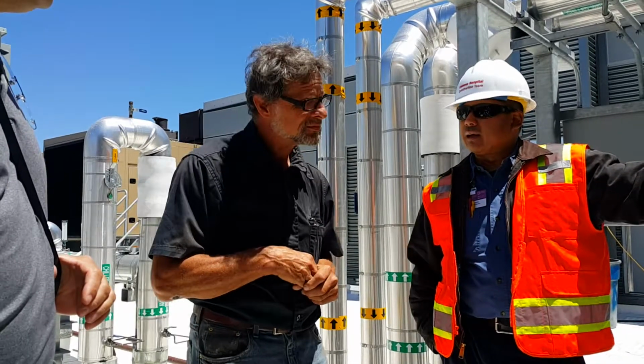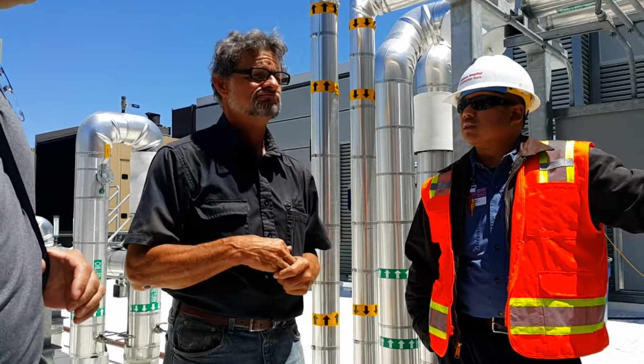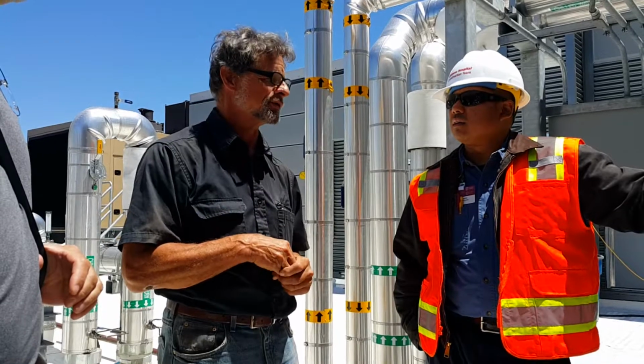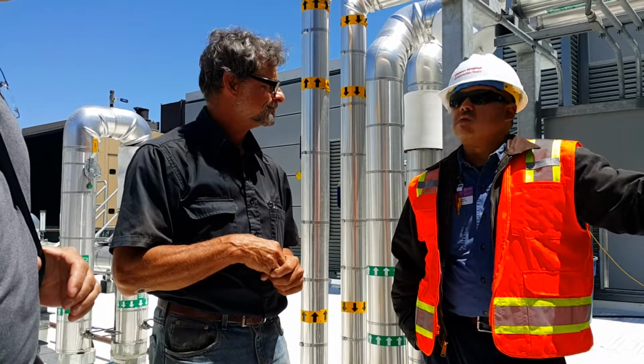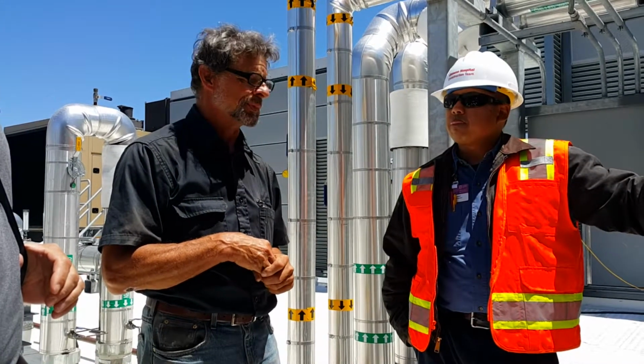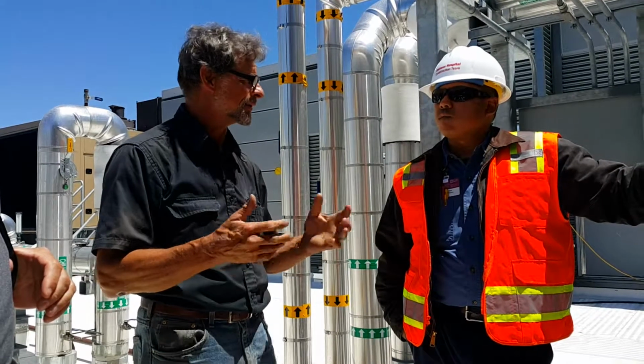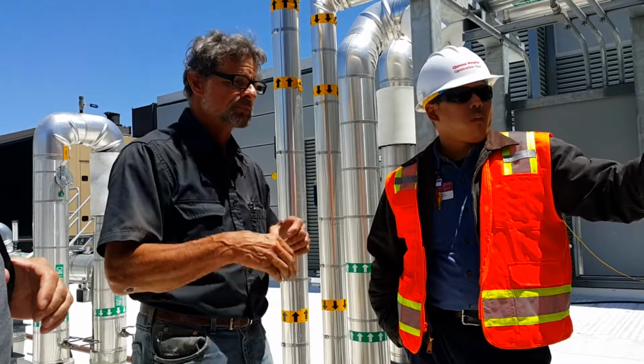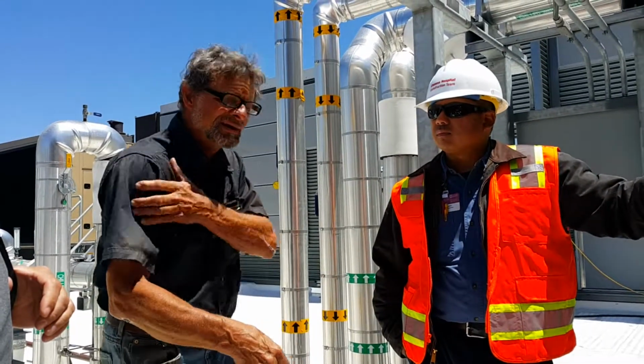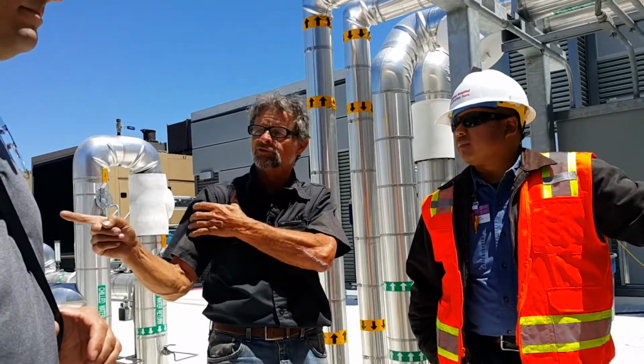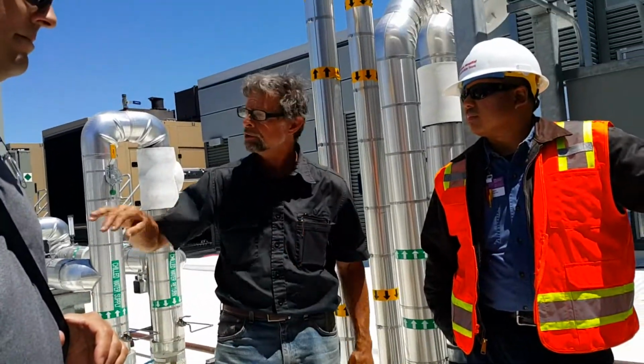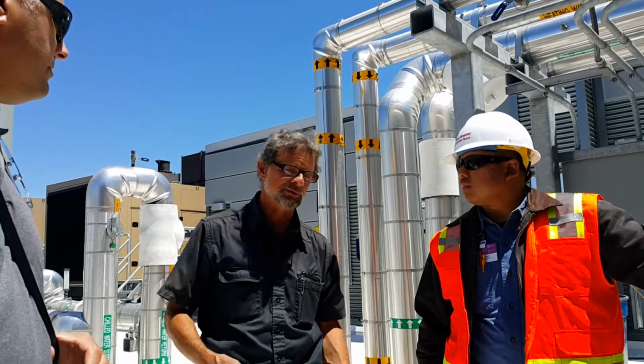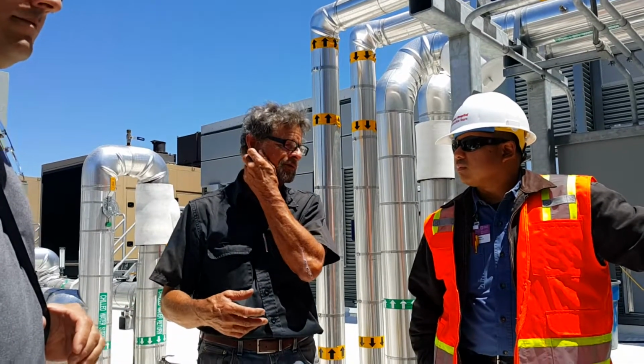What is it normally running at? Depends on your load. You know how many boxes are open and cooling, wide open or closed down. You're probably going to control duct static. The OR is probably going to be full outside air and constant volume. The only reason you put a drive on that is to compensate for filter loading.